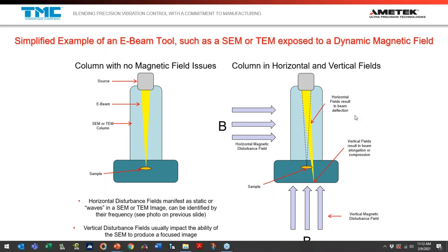How do these affect e-beam tools? Let me give an oversimplified example of an electron beam tool. In any electron beam tool you have three important parts: your source, your column, and your sample in the sample chamber. The electron source can be anything from a plasma gas emission to a tungsten filament, generating electrons that form an electron beam sent down through the column. The beam gets focused through magnetic optics — magnetic coils that generate their own fields — to focus, move, and control the beam, which is then incident on a sample where secondary electrons are generated and detected to produce an image.